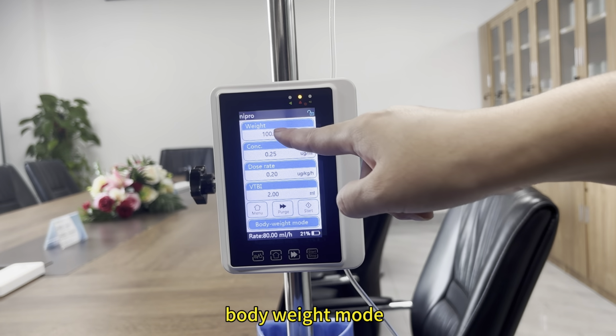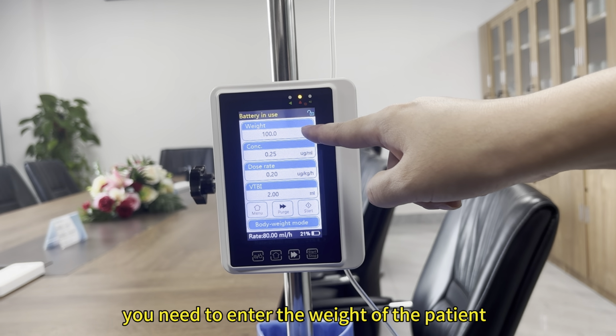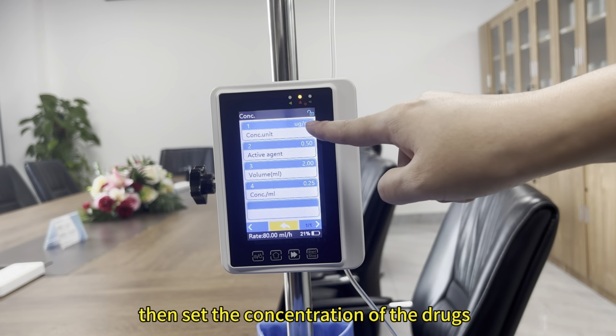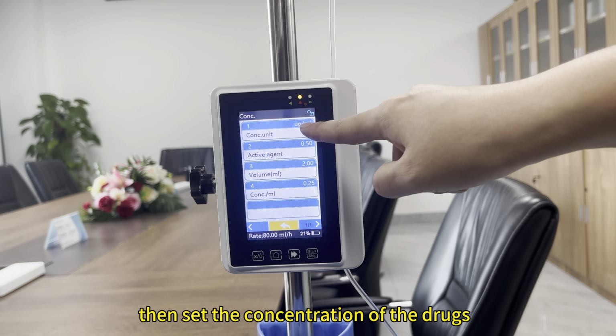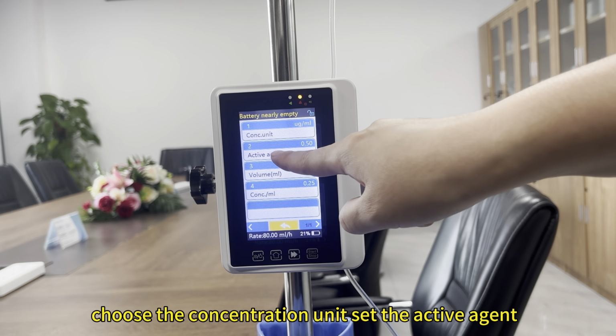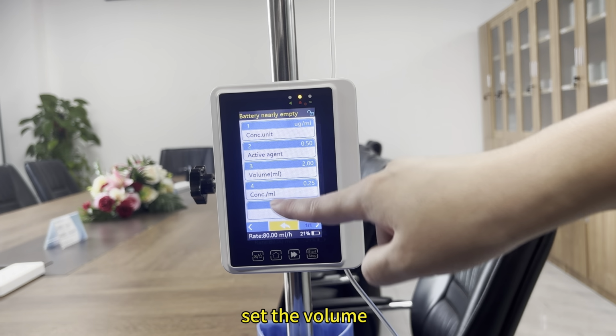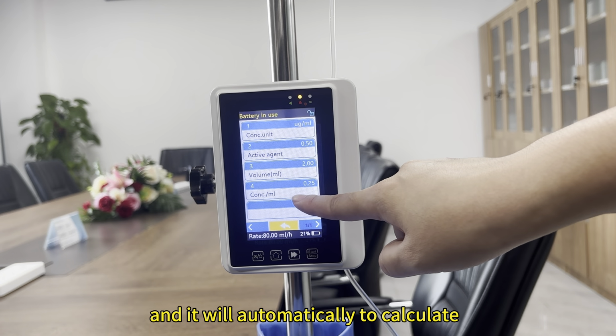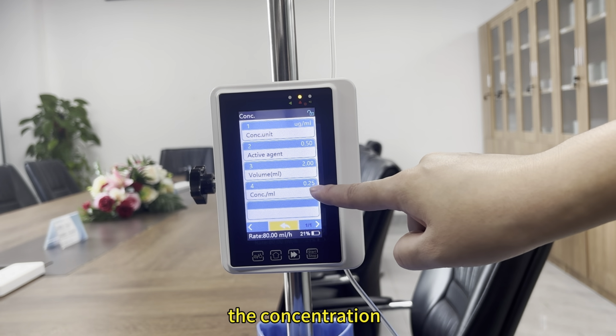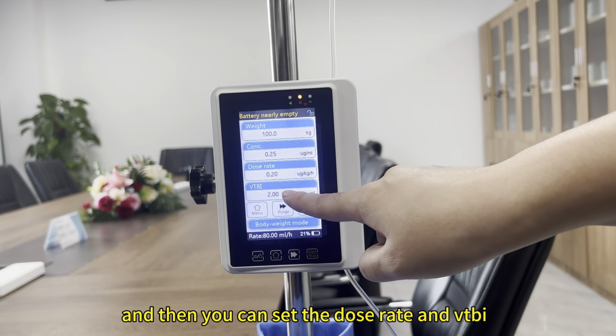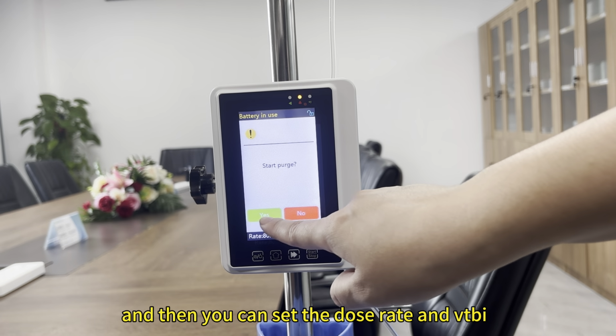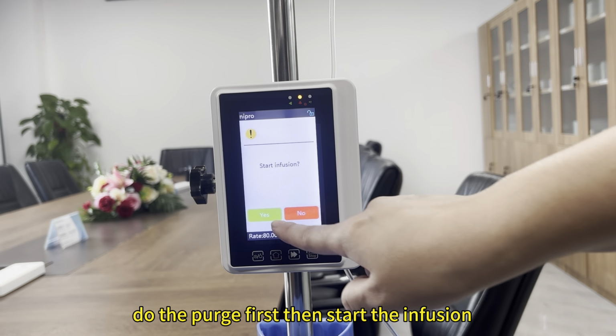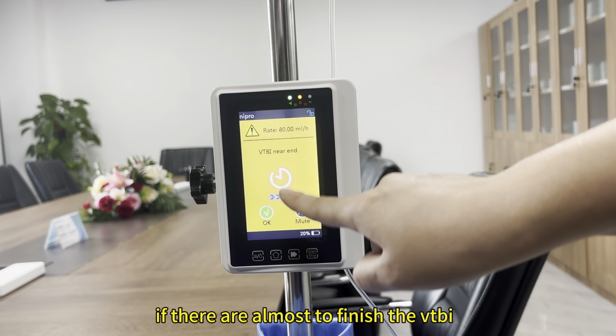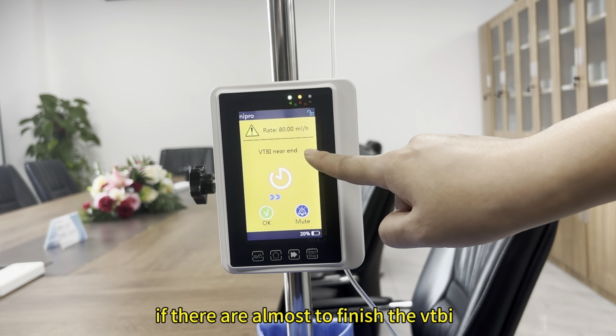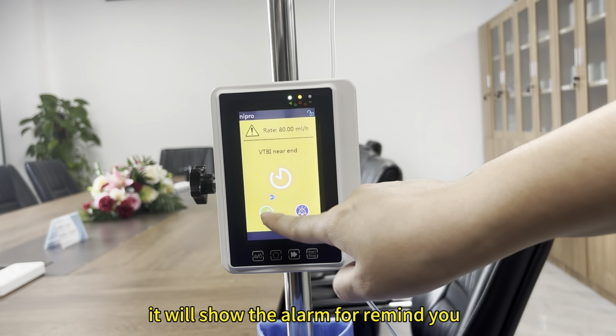Body weight mode. You need to enter the weight of the patient. Then set the concentration of the drugs. Choose the concentration unit, set the active agent, set the volume, and it will automatically calculate the concentration. And then you can set the dose rate and VTBI. Do the purge first, then start the infusion. If it is almost finished with the VTBI, it will show an alarm to remind you.